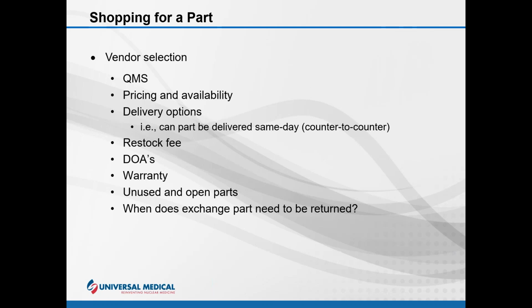Ask your preferred vendor about their QMS or quality management system. This is a good indication that policies and procedures are in place to ensure a successful supply chain management system. Pricing and availability. Typically, vendors base their pricing off of the OEM price. This usually will be somewhere in the area of maybe 40 to 60% off of the OEM. And availability can be an issue on certain parts, let's say with high failure rates. Example would be maybe a GE Infinia and GE MG. The hand controls are a high failure rate. But usually this is only with newer systems or obsolete systems.